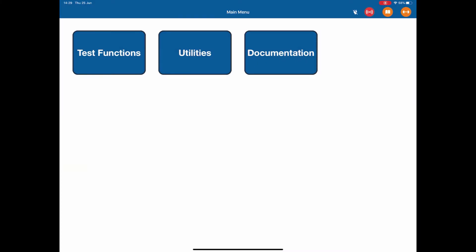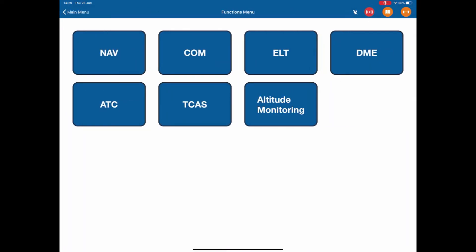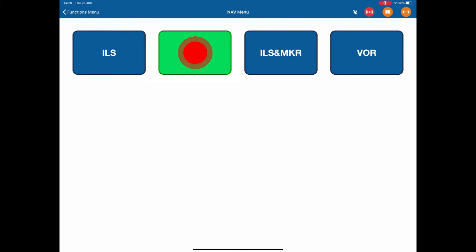In this case, we're going to do a marker beacon test. To get to the marker beacon test, I hit the test functions, navigation, marker.